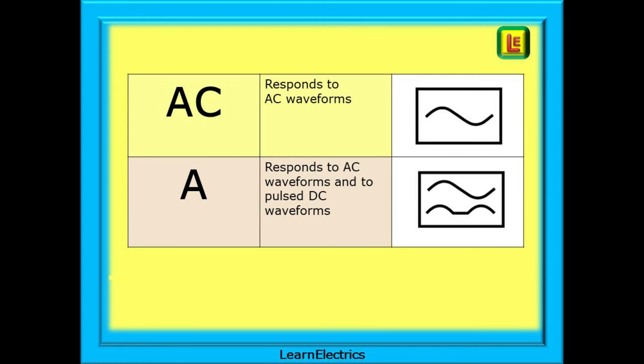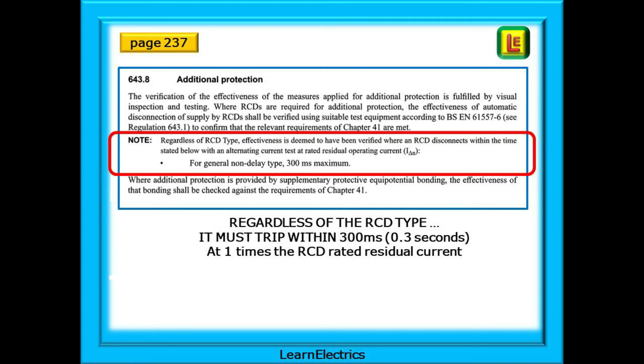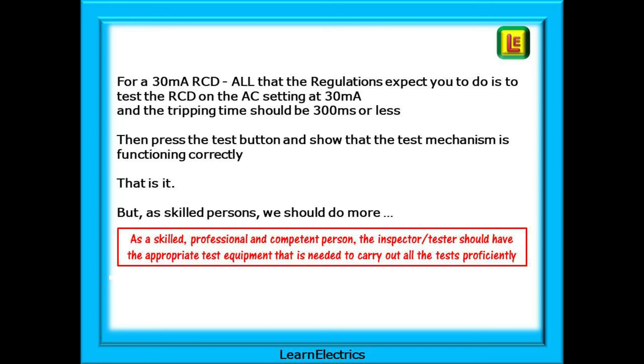Looking at type AC and type A RCDs, they will be marked with the symbols shown here. The AC type only responds to AC waveforms, whereas the type A responds to AC waveforms and to pulsed DC. Take a look at page 237 of the wiring regulations book — section 643.8 states that regardless of the type it must trip within 300 milliseconds with a test current of one times the RCD rated residual current. For a 30mA RCD, all that the regulations require is to test the RCD on the AC setting at 30 milliamps with a tripping time of 300 milliseconds or less, then press the test button to show the test mechanism is functioning correctly.